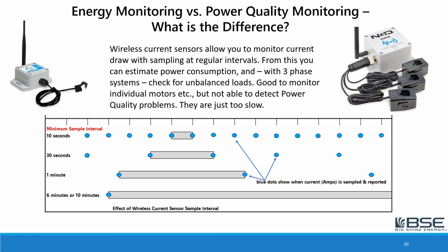So the little blue dots on this line chart are meant to indicate the typical sampling intervals, meaning that the fastest one I saw in the market was every 10 seconds. It will send a signal saying, this is how many amperes I'm measuring. In between, it doesn't record anything. It just sends a blip, blip, blip. The next fastest was every 30 seconds. After that, 1 minute, or after that, 6 minutes or 10 minutes, and some are like 30 minutes.